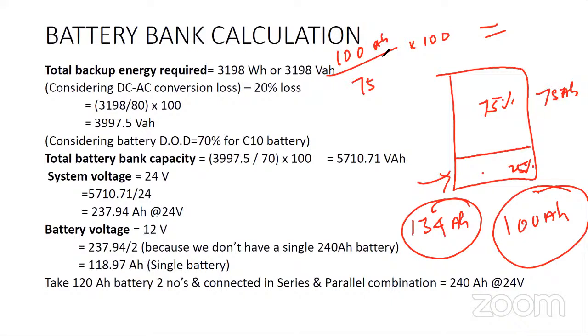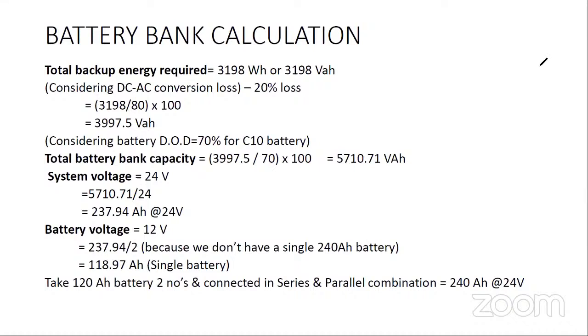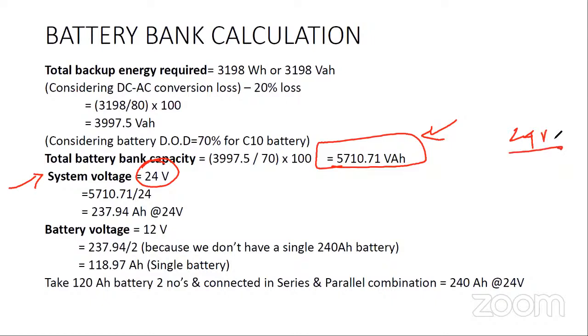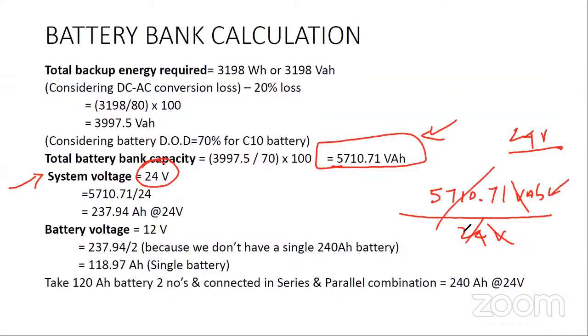So this is how we are arriving at the total battery bank capacity. Now we know that the system voltage is 24 volts. Now we are in the situation of sizing the battery and connecting the battery. We know that this is the battery bank and 24 volts is the system voltage. Now how to size? If I divide the energy, volt-ampere hour, by 24 volt, the volt will get cancelled and what you get is the ampere hour. If you divide, what I'm getting is 237.94 ampere hour at 24 volt configuration.